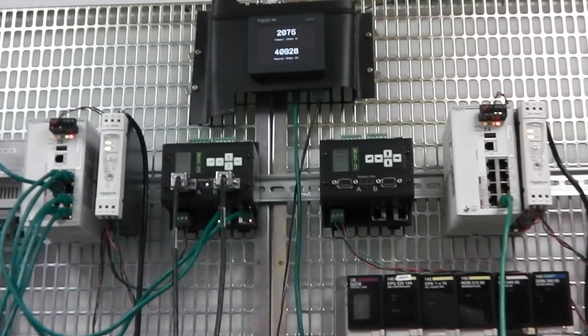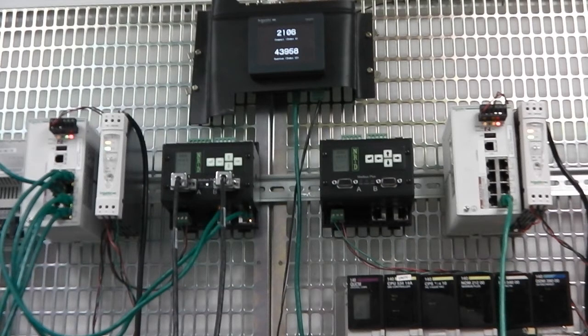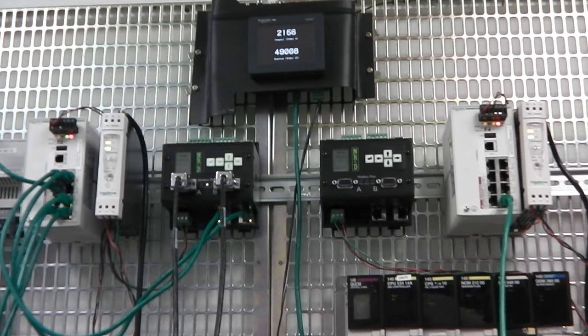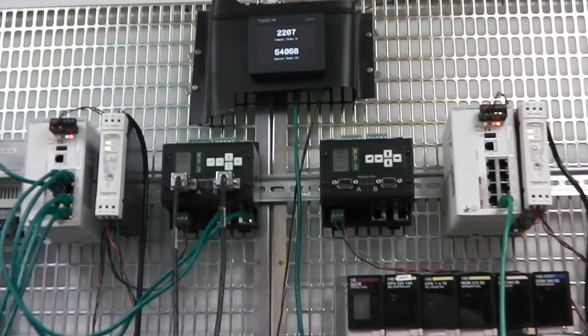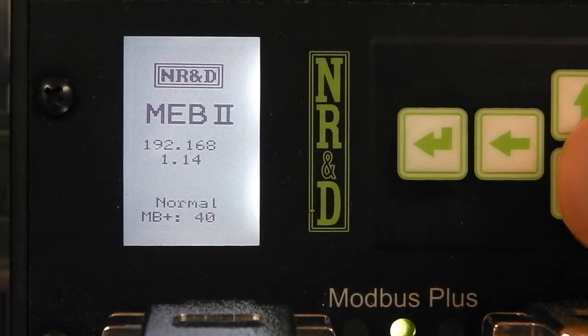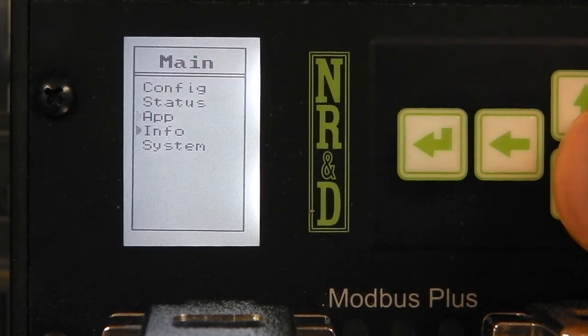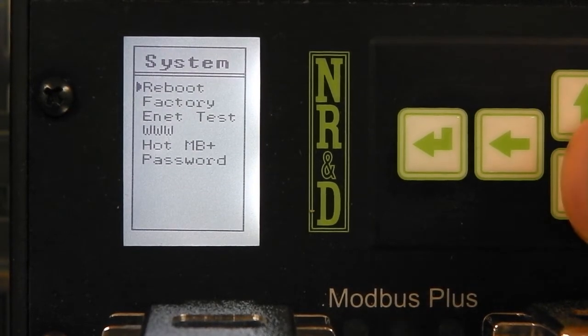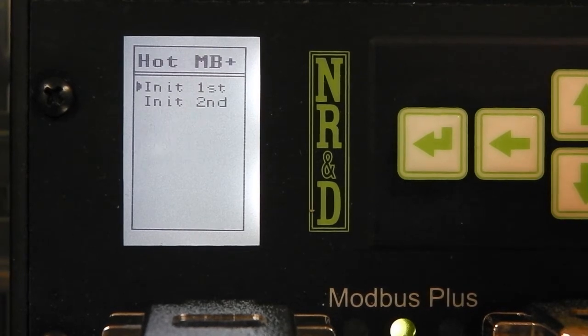A second MEB2 is added to the system along with a second power supply and Ethernet switch. First we configure the original MEB2 for Hot Modbus Plus operation. This is very simple through the front panel. Just initialize it to first and wait for the unit to reconfigure itself.